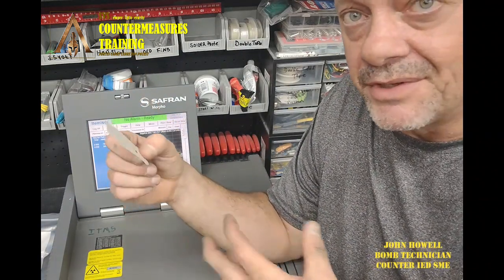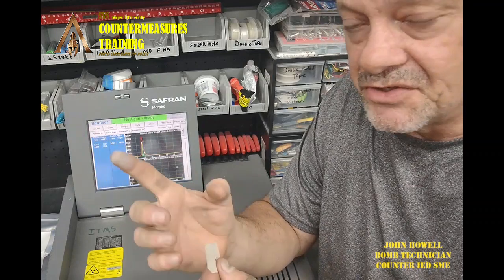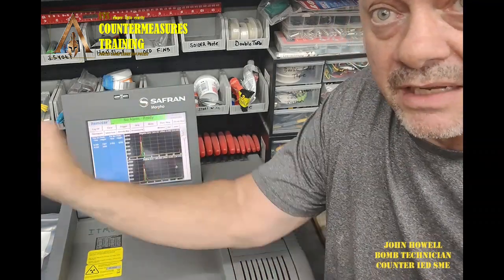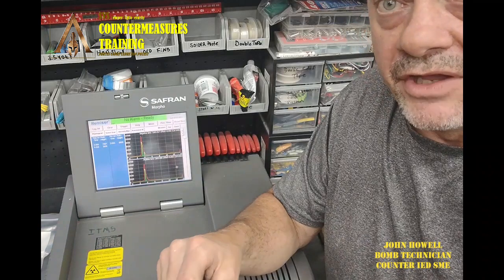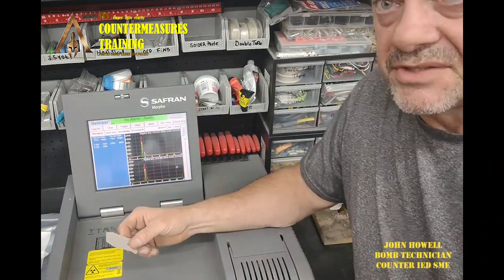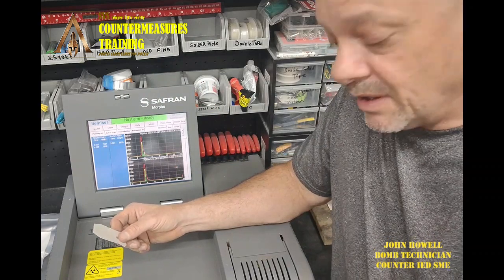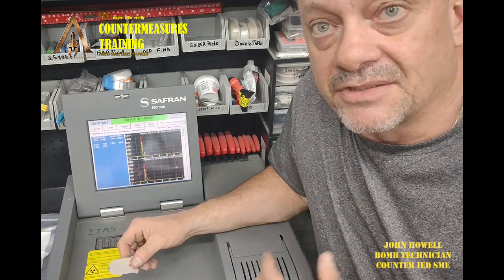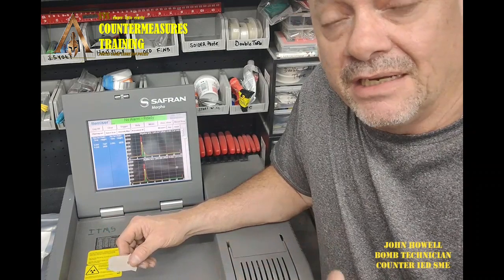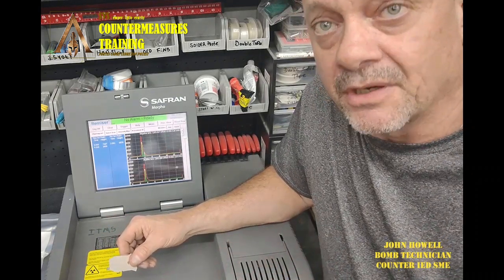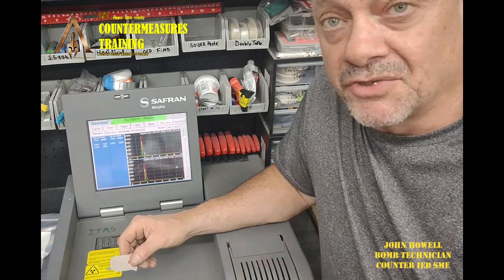Some of the systems will have you use a wand. A lot of places they'll just use their finger, and you'll do it by hand, by what we call hand sampling. And then you'll take and place the sample inside the system into what we call the desorber. Now the desorber is basically a toaster. It's a heater, and it's heated up to a specific temperature based on what you're actually trying to do.